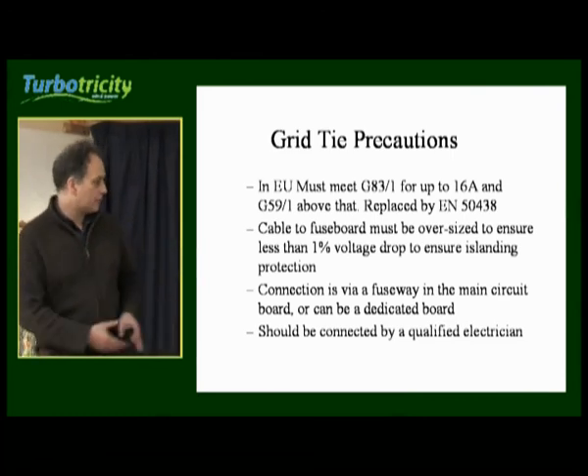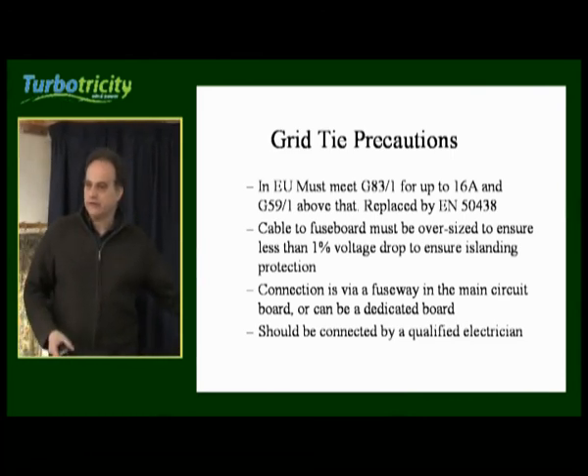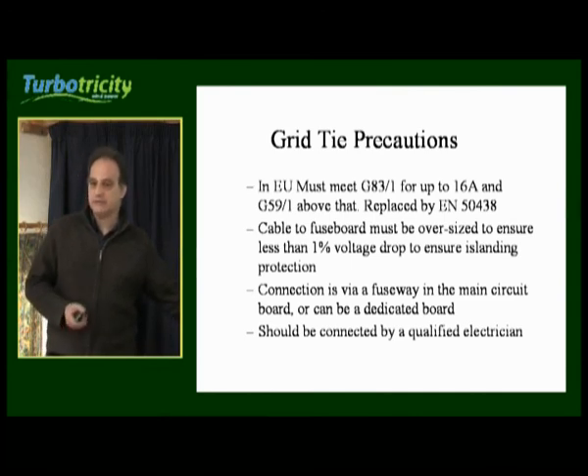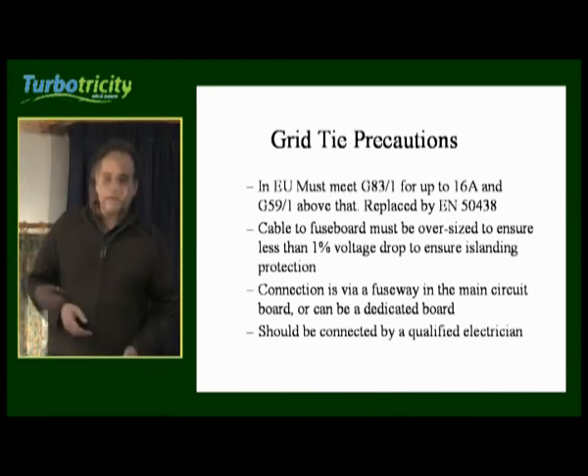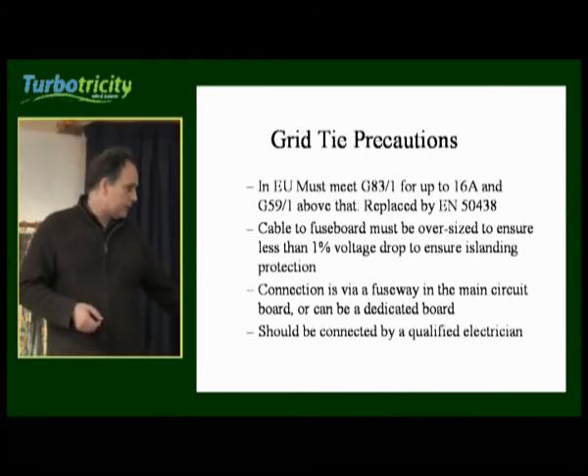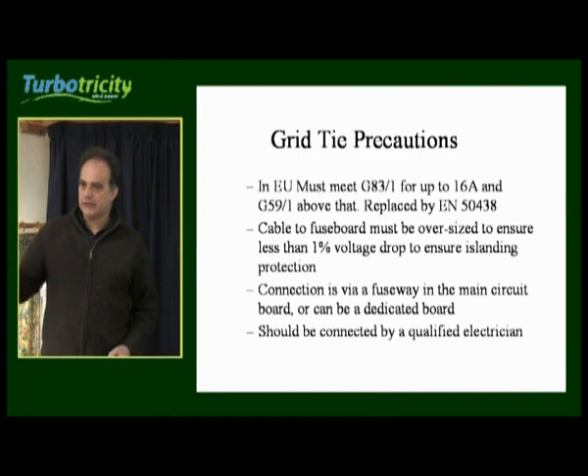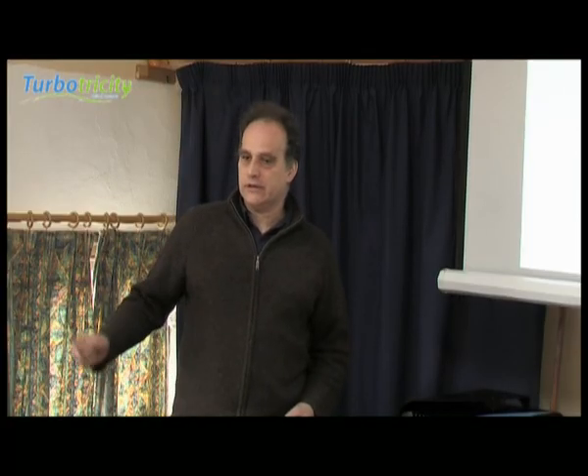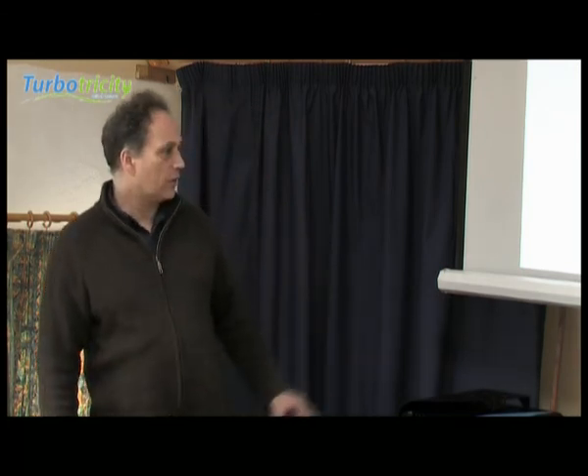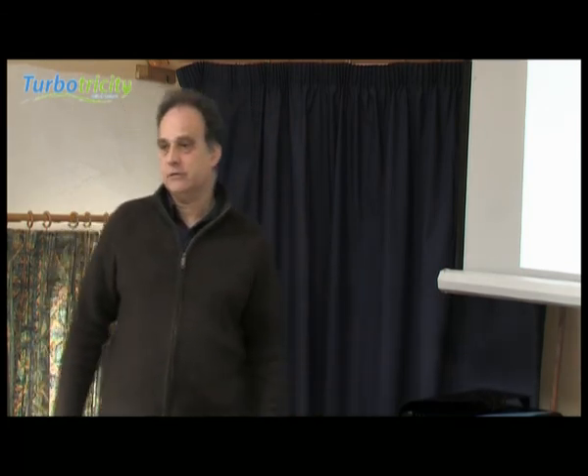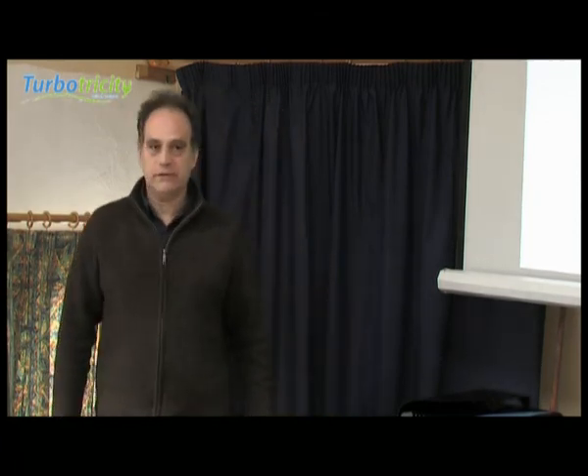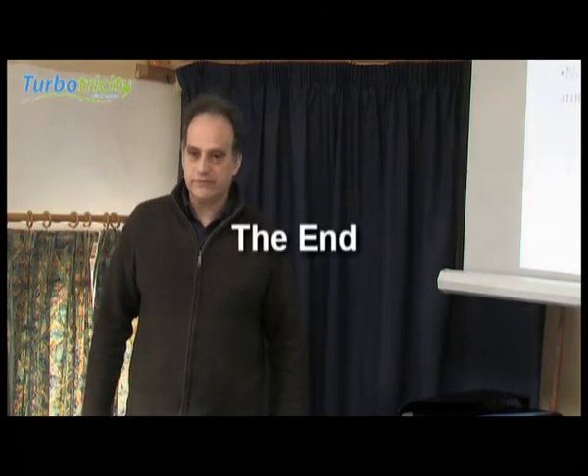The cable between the inverter and the fuse board must be sized such that there's no more than a 1% voltage drop across that cable — which is easily met provided it's in the same room. Normally you connect this quite simply into a fuseway in the consumer unit, putting in another MCB and connecting it in there. The electricity then seamlessly goes up or down the wire, either into the household supply or back out into the grid according to whether it's needed. All of that connection work has to be done by a registered, qualified electrician — the utility is going to insist on that for safety reasons.